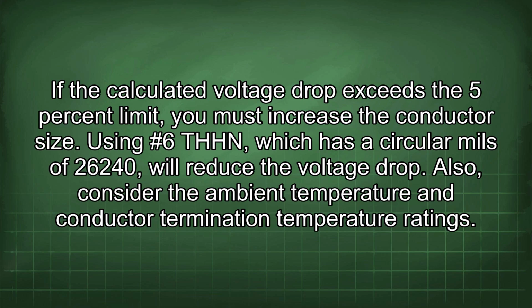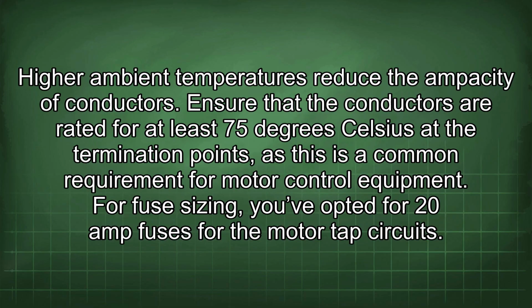Also, consider the ambient temperature and conductor termination temperature ratings. Higher ambient temperatures reduce the ampacity of conductors. Ensure that the conductors are rated for at least 75 degrees Celsius at the termination points, as this is a common requirement for motor control equipment.